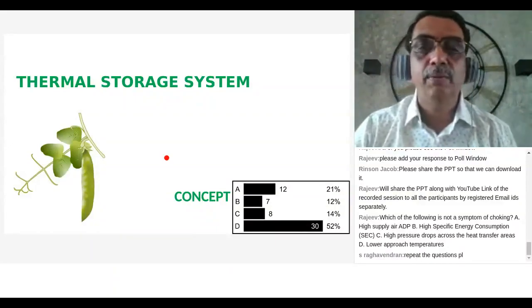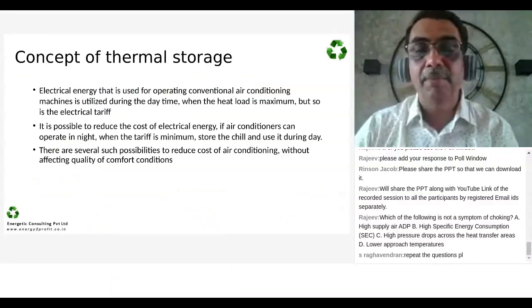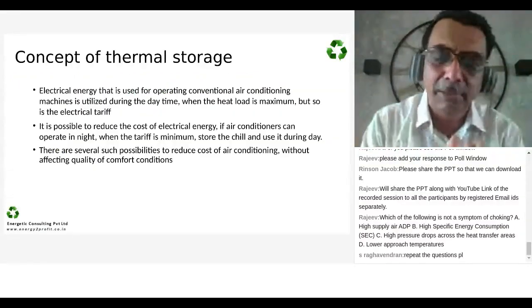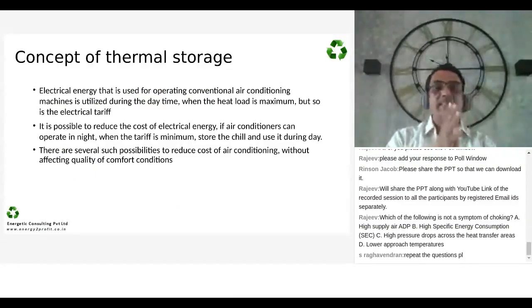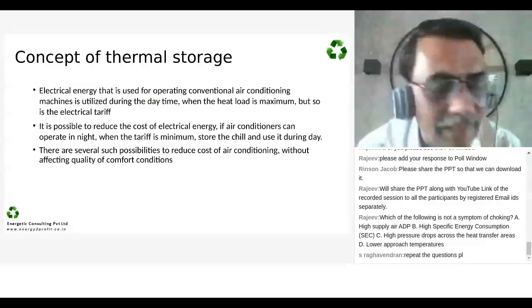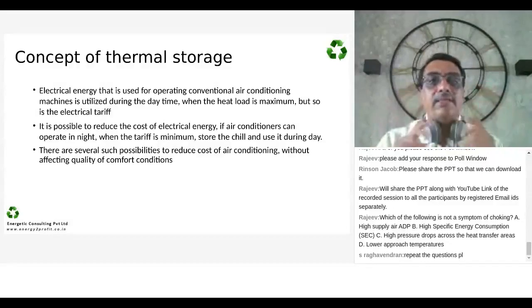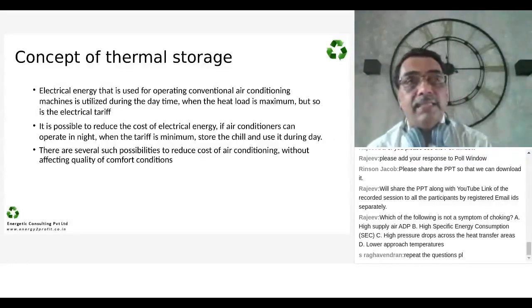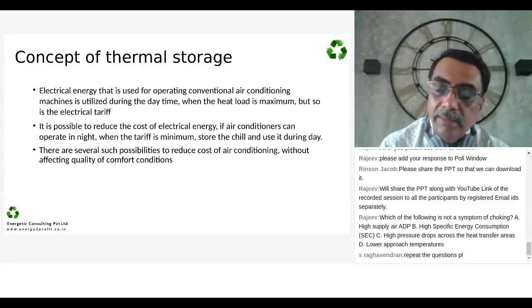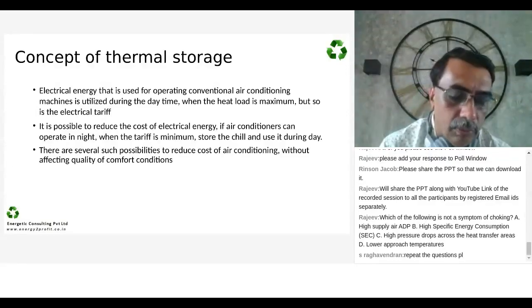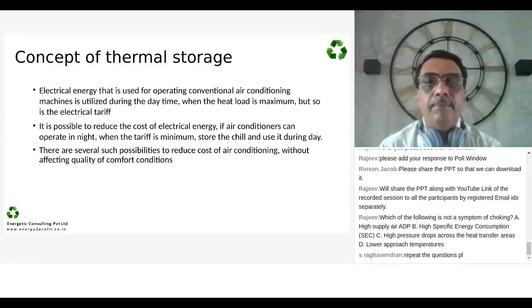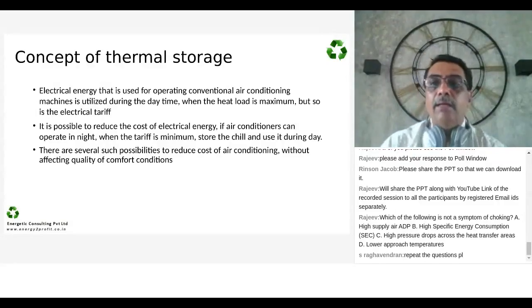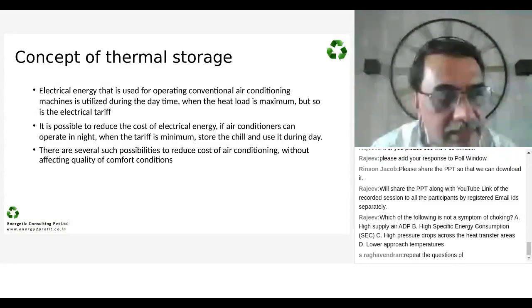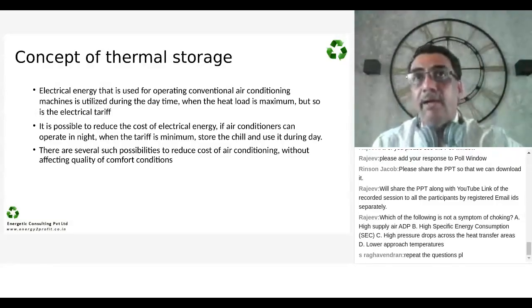Thermal storage system. Has anybody ever operated a thermic fluid system, a thermal storage system, a hot and cold chill storage system? Now, thermal storage is nothing new, it's an ancient thing. In our dairies, we used to do it forever. What is done? We keep ice as a storage. Instead of keeping chilled water circulation, we keep ice as a storage in a tank. That ice melts and the molten ice cools the circulating water even when the chiller is not working. Which means that definitely this is not something unknown. Right? Now, do you require less energy to make ice than chilled water? Answer is no. You require higher energy to make ice.